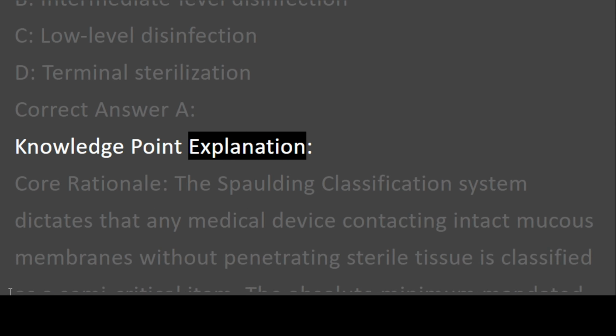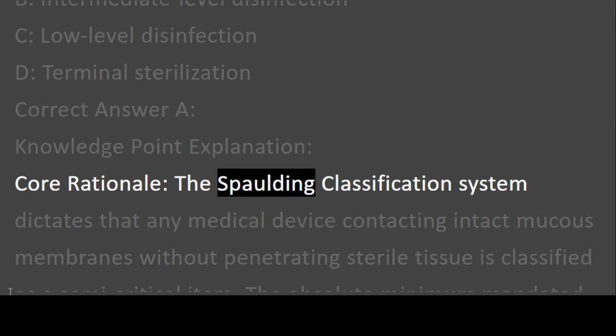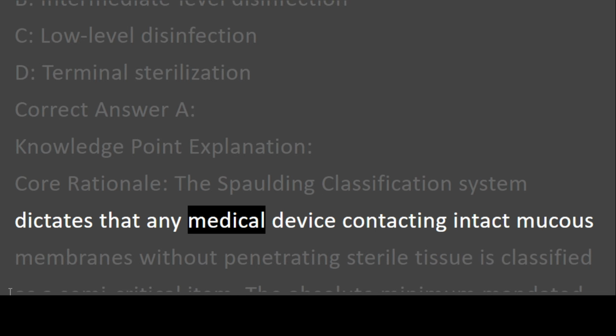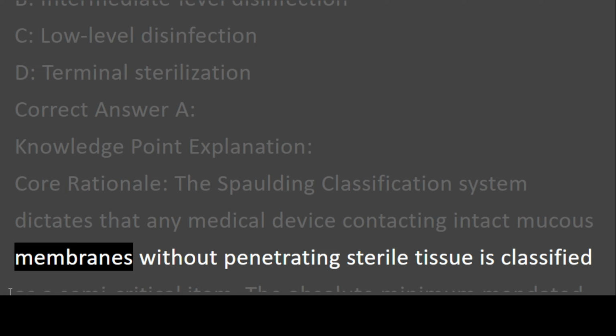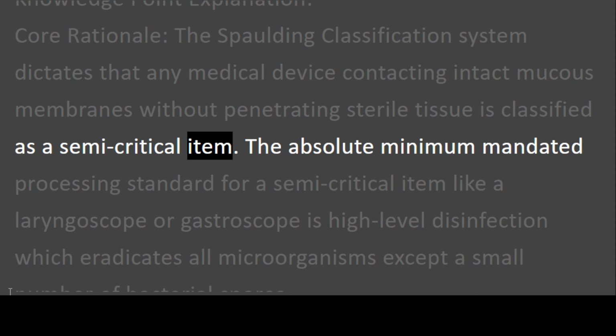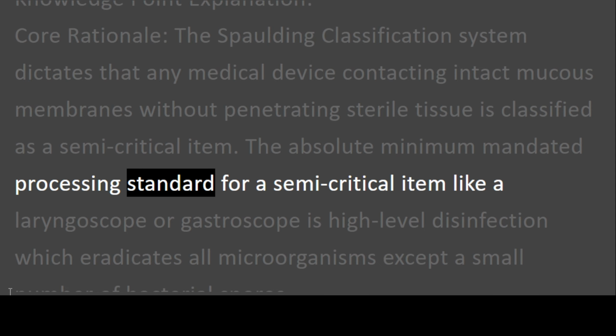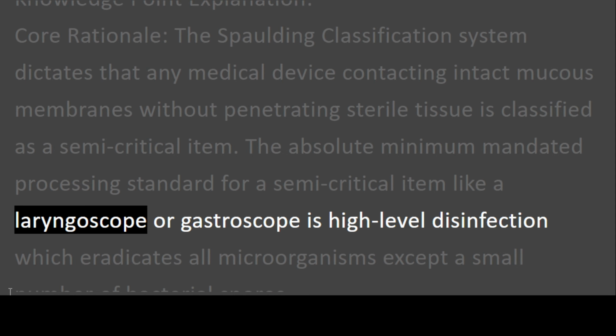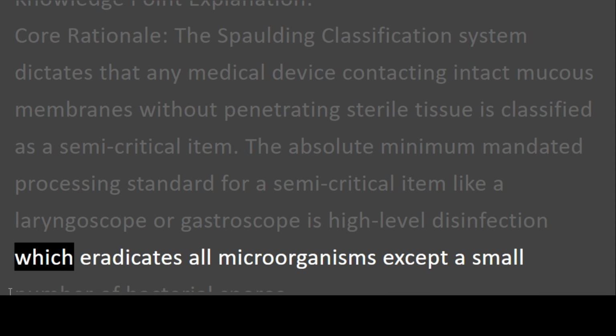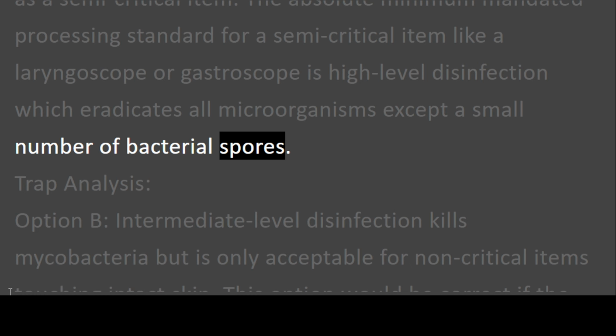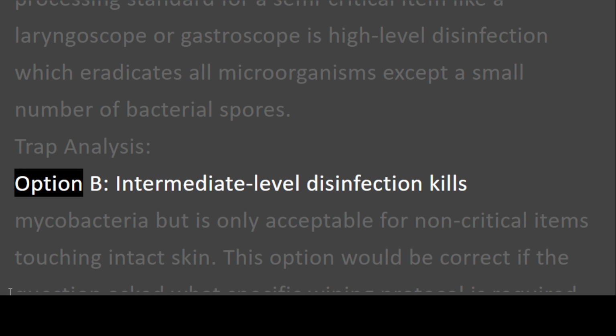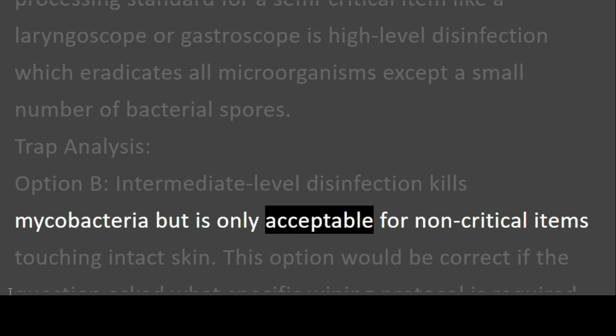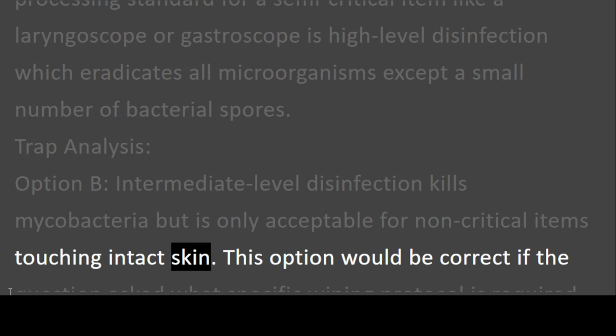Knowledge point explanation. Core rationale. The Spaulding classification system dictates that any medical device contacting intact mucous membranes without penetrating sterile tissue is classified as a semi-critical item. The absolute minimum mandated processing standard for a semi-critical item like a laryngoscope or gastroscope is high-level disinfection, which eradicates all microorganisms except a small number of bacterial spores. Trap analysis. Option B. Intermediate-level disinfection kills mycobacteria but is only acceptable for non-critical items touching intact skin.